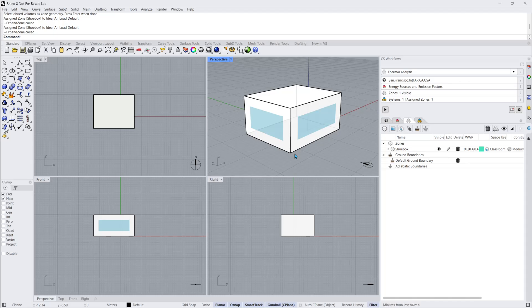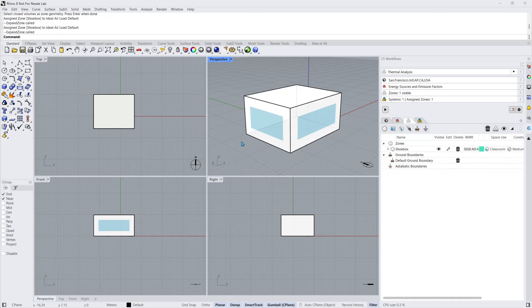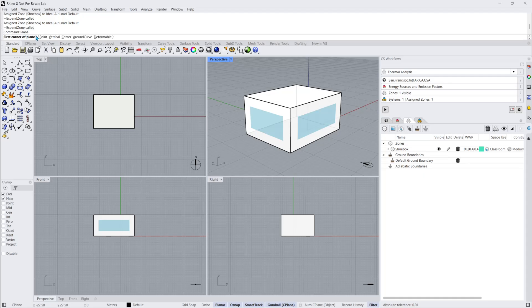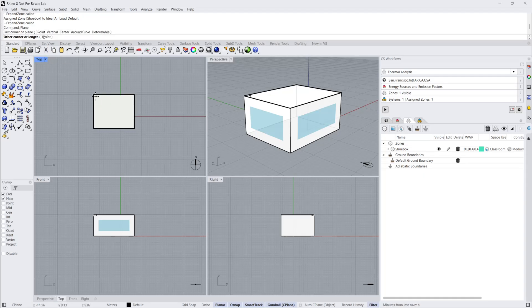Let's set some adiabatic adjacencies. If a surface is defined as adiabatic, it will transfer no heat during the simulation. To add adiabatic surfaces, you'll have to create separate surfaces that are adjacent to the zone. I'll quickly create three surfaces using the plane command on my roof and the two walls with no windows. This will create a corner ground condition in a conceptual multi-story building.